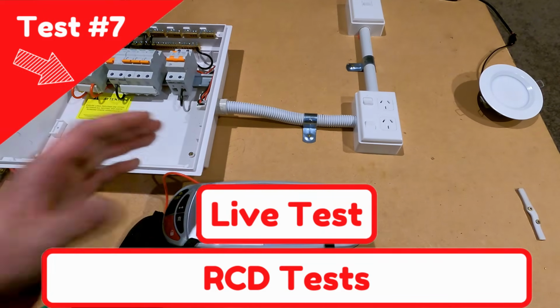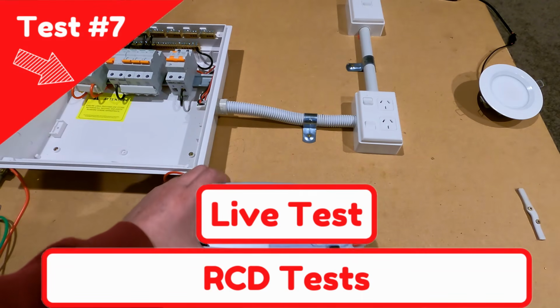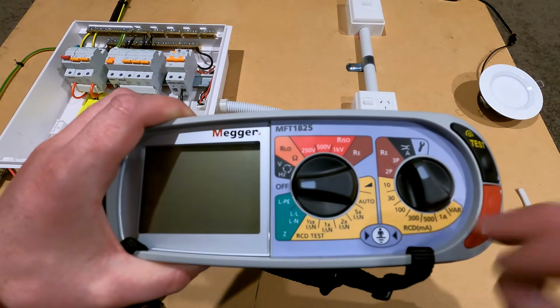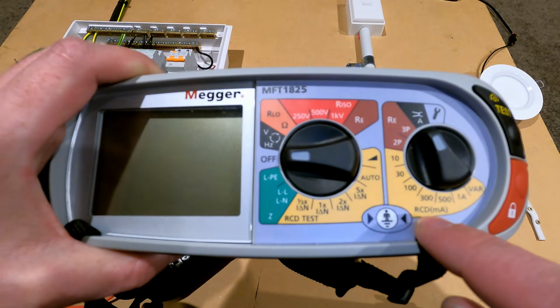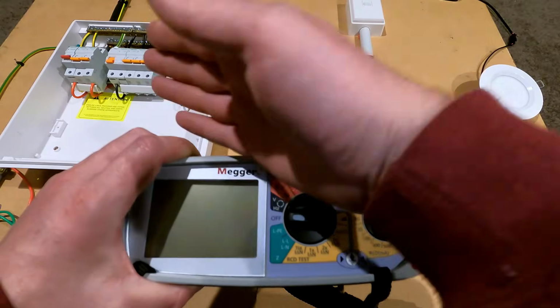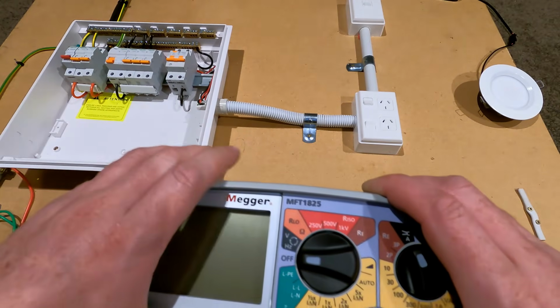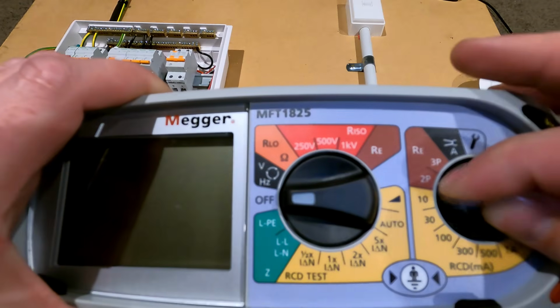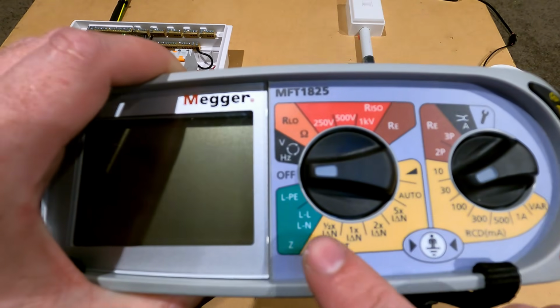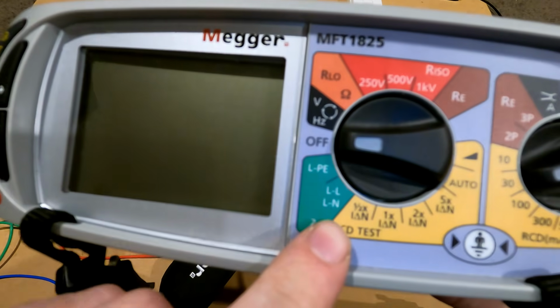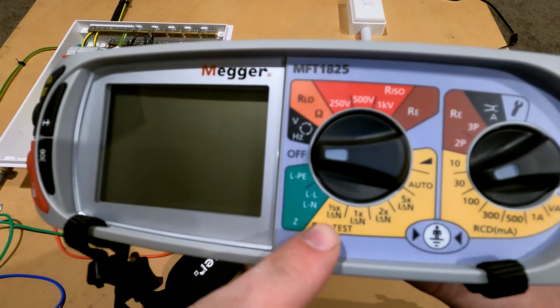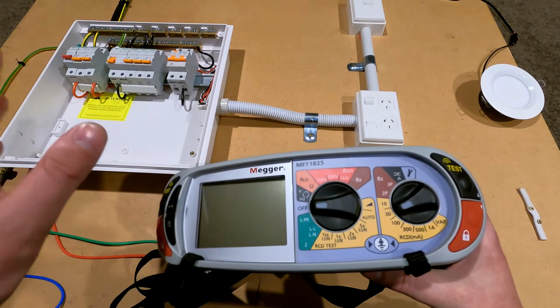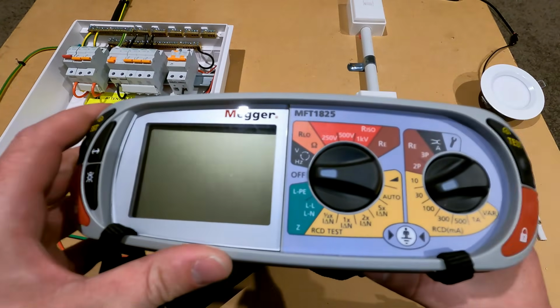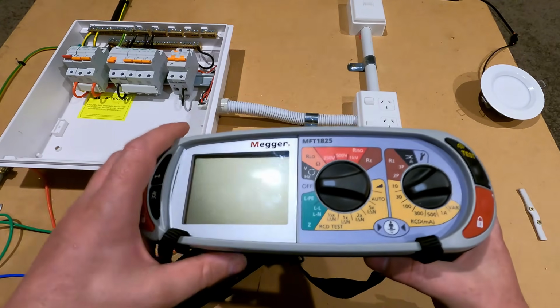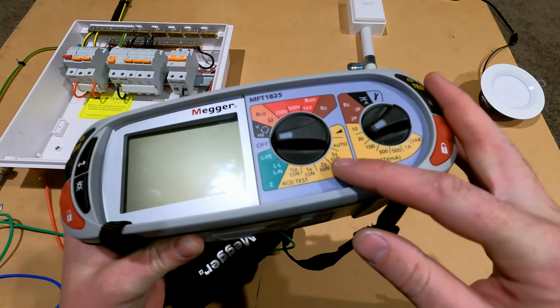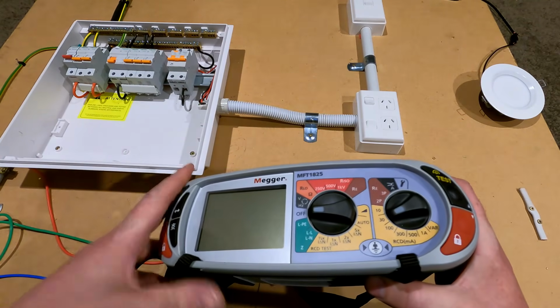Alrighty, so the next lot of tests are going to be our RCD tests. For these, we use these yellow areas on the multifunction tester. The first one you want to set is your RCD milliamp ratings. Now we've already verified that our RCD and our RCBO are both 30 milliamps. So we'll turn this dial to the 30 milliamp dial, and then we're going to run through these tests one by one. So our test here at half the rated current, so 15 milliamps, we expect that these two units will not trip at all. Otherwise they are defective. At 1 times the current, we expect that these will operate under 300 milliseconds. Then we're going to do the 5 times test, which we expect these two to operate under 40 milliseconds.